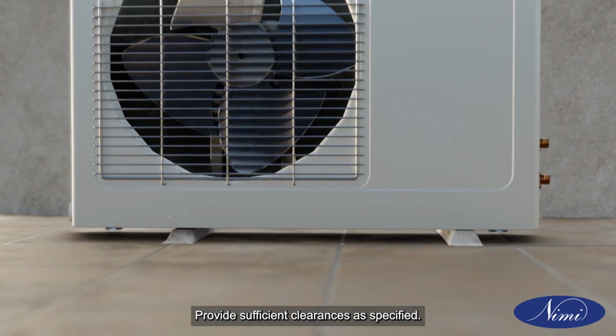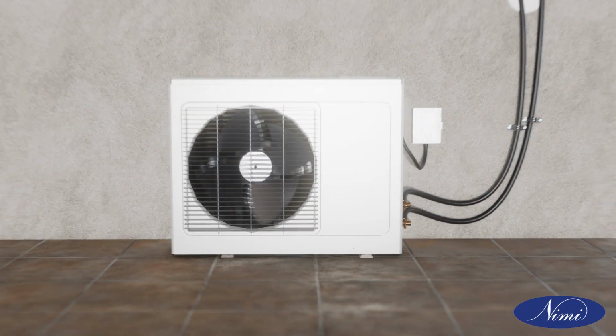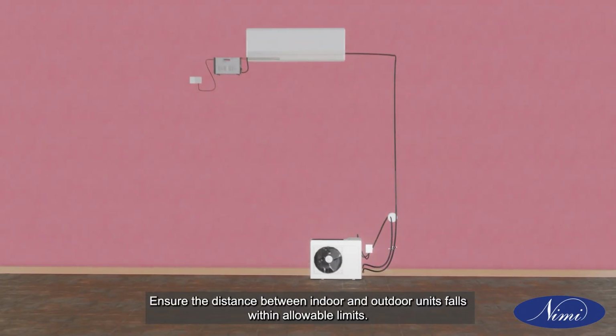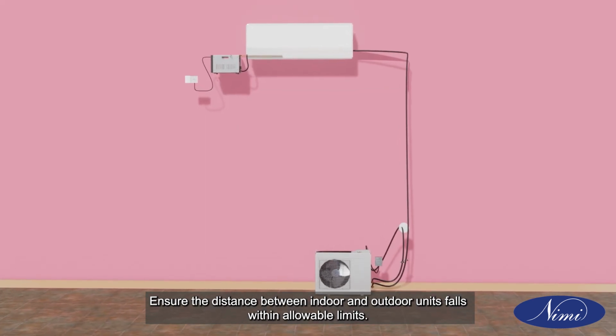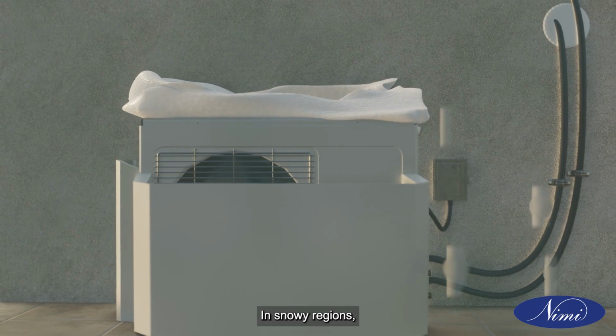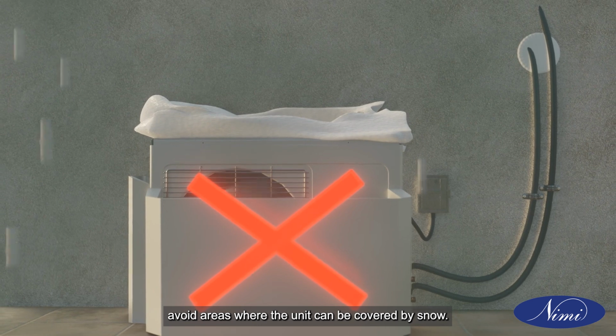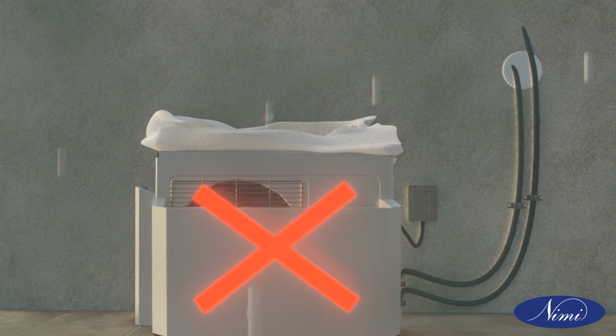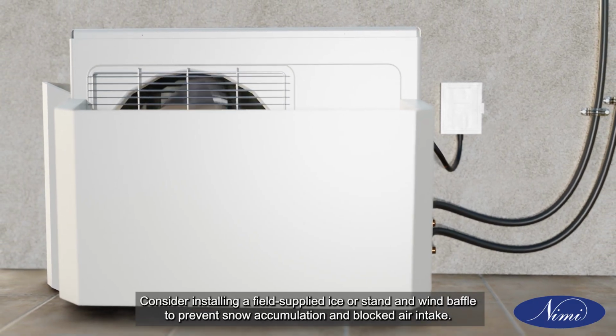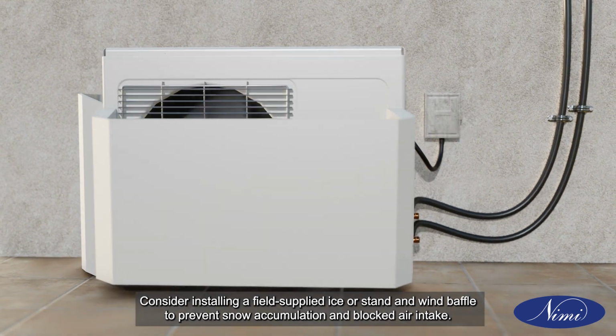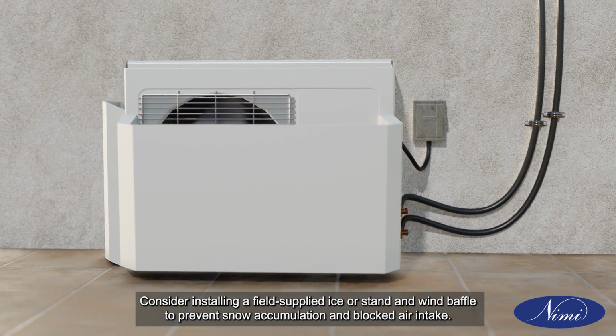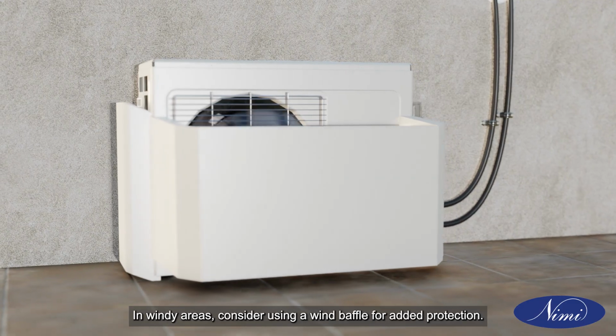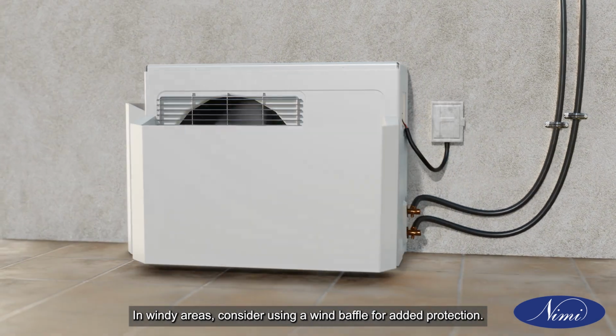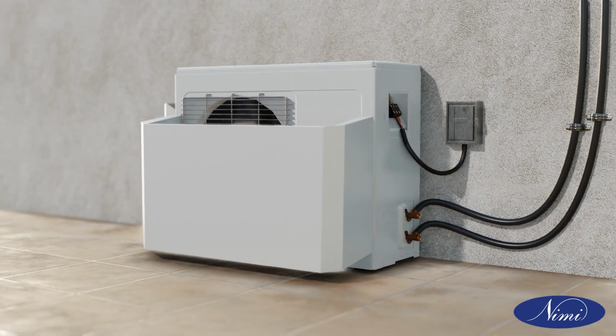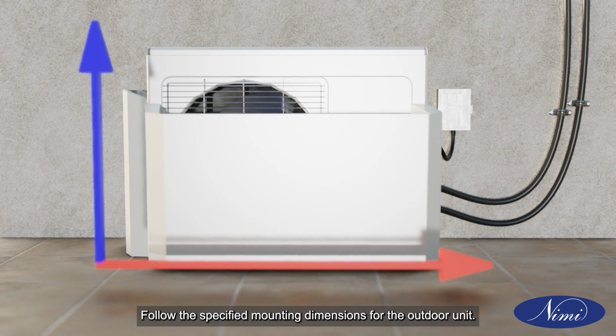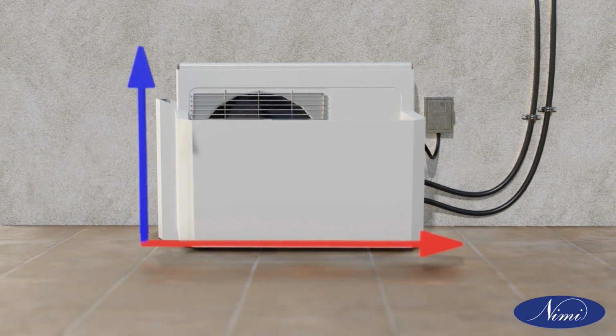Provide sufficient clearances as specified. Ensure the distance between indoor and outdoor units falls within allowable limits. In snowy regions, avoid areas where the unit can be covered by snow. Consider installing a field-supplied ice stand and wind baffle to prevent snow accumulation and block air intake. In windy areas, consider using a wind baffle for added protection. Follow the specified mounting dimensions for the outdoor unit.